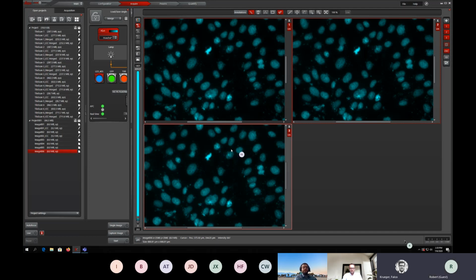And still, you have quite a nice dynamic range. On the left-hand side, there are not only those small buttons that show you the brightest and darkest pixels, those values are also given. The brightest pixel in the shortest exposure here is 1400 as an intensity value, and the darkest pixel, the background, is 200. What always gives you a rough estimate is to divide the smaller number by the bigger number. So here it's a signal to background ratio of 7:1, roughly, and this is a value that you can optimize your imaging settings with.